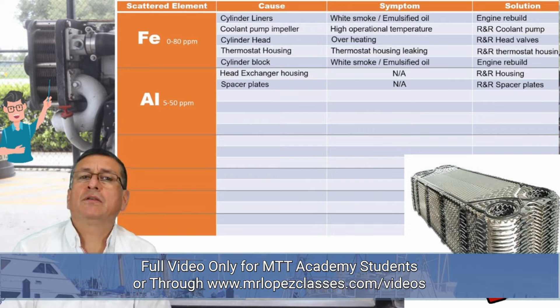Once again, you probably don't have any symptom, but you can see leaks. You'll notice the coolant level decrease in the reservoir, and the recommendation is to replace the plates. When you order the kit for this type of heat exchanger, you receive the complete kit with all the plates and gaskets, and you need to replace those plates.